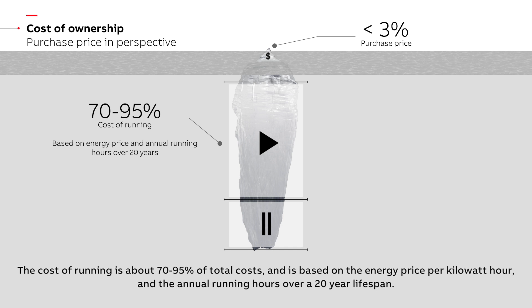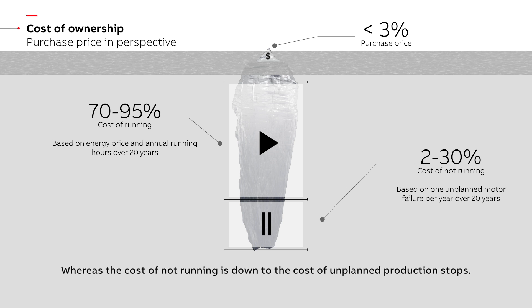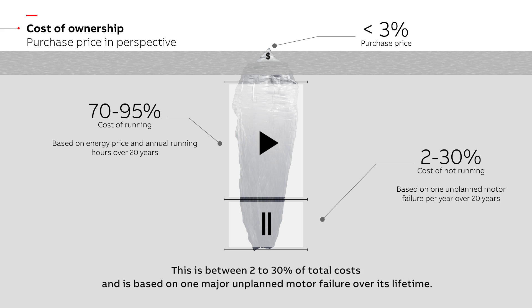The cost of running is about 70 to 95 percent of total costs and is based on the energy price per kilowatt hour and the annual running hours over a 20-year lifespan. Whereas the cost of not running is down to the cost of unplanned production stops — this is between 2 to 30 percent of total costs and is based on one major unplanned motor failure over its lifetime.